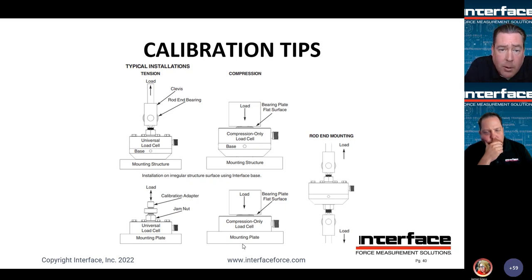And then on the bottom left there, last one I'll talk about here is an example of a typical load cell, how it is fixtured into the string, and you'd have a jam nut to a male calibration adapter. Again, jam nut and calibration adapter jammed above capacity. So typically we take that to between 125 and 140% of applied load, and then jam the jam nut at that point. So we do not have that jam nut coming loose above the calibration, or below the maximum calibration load, I should say. Next, please.